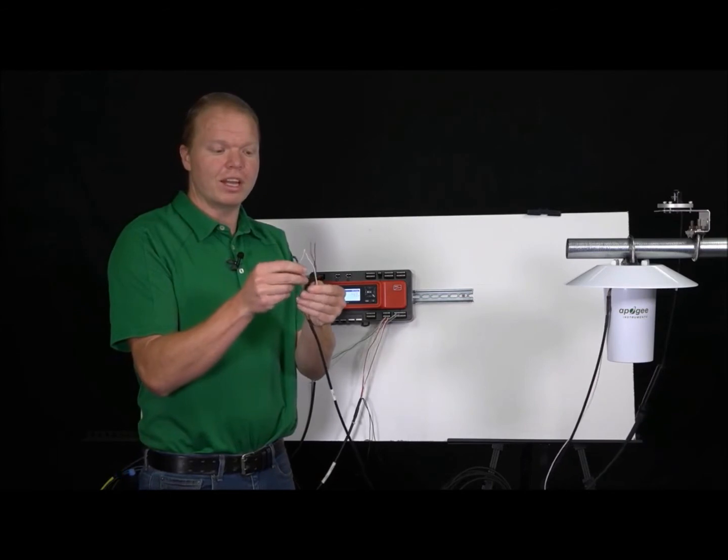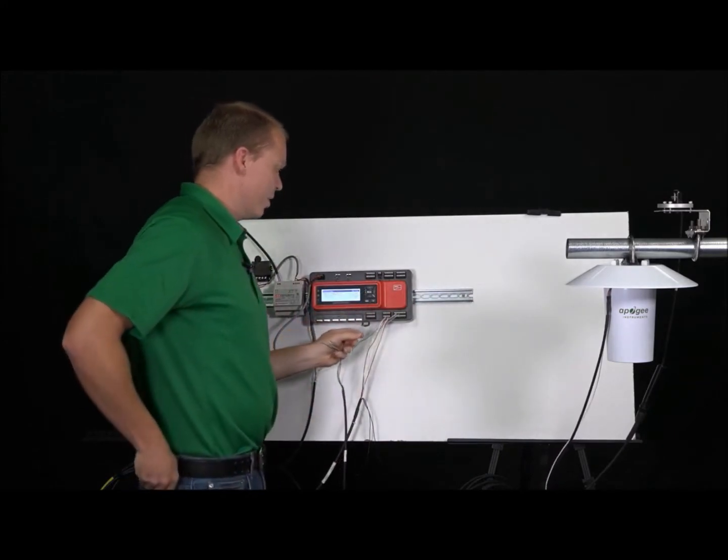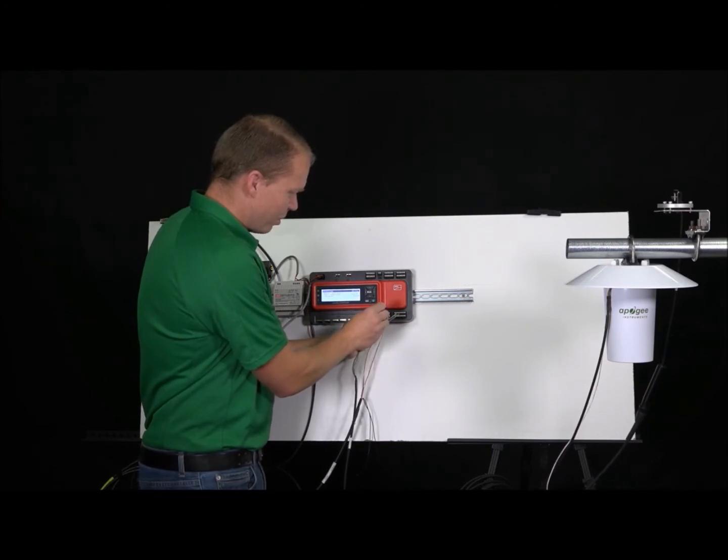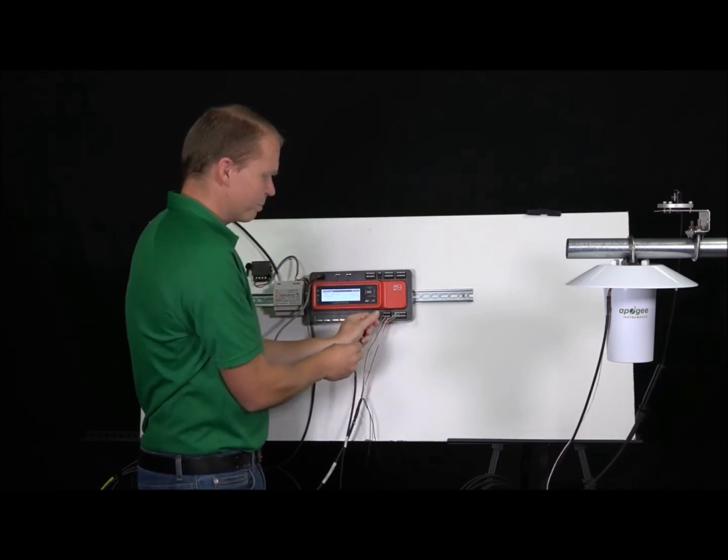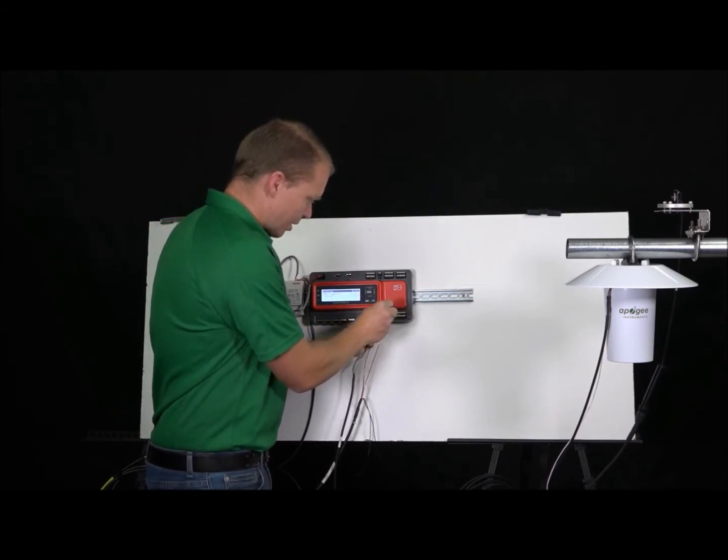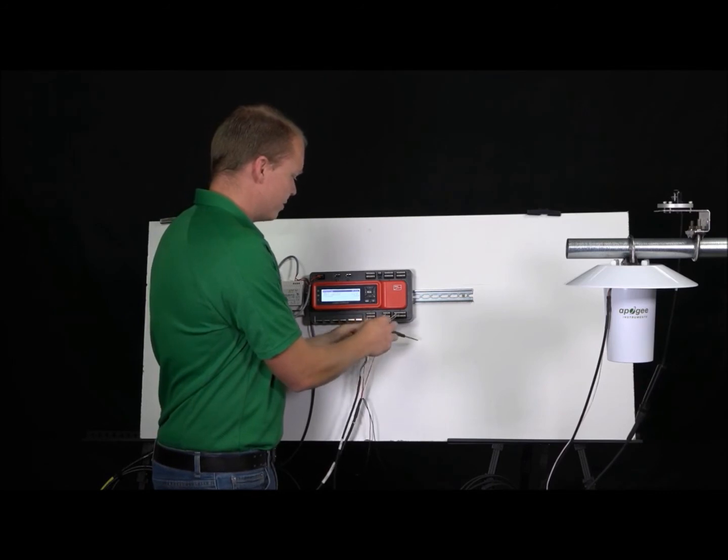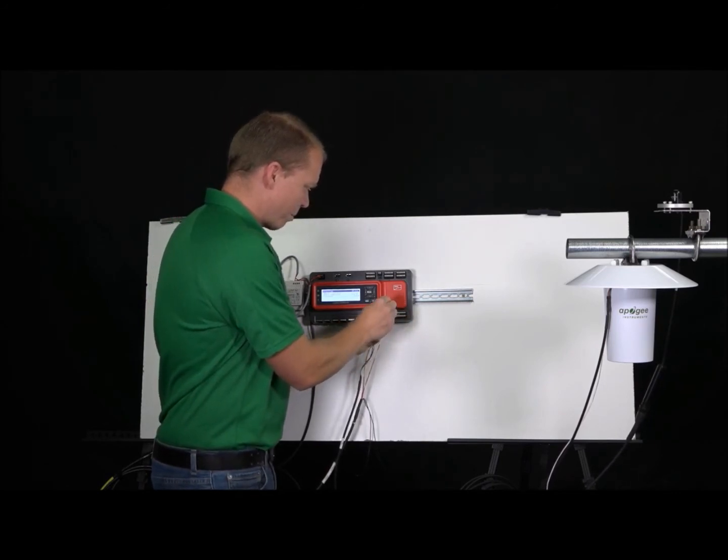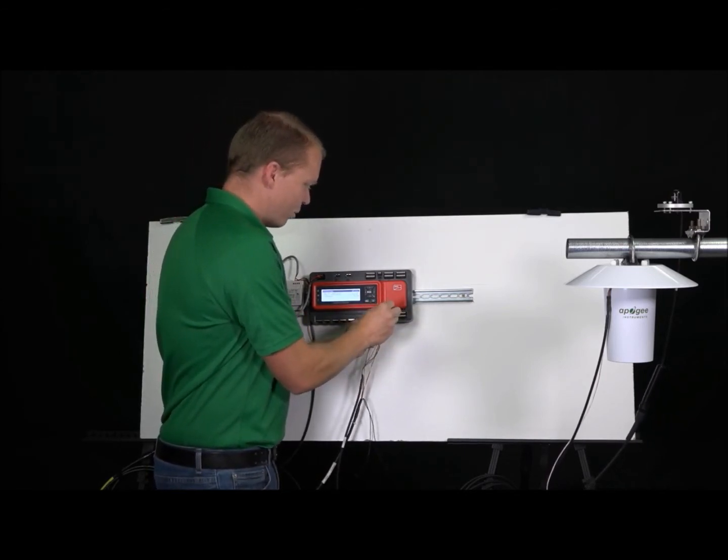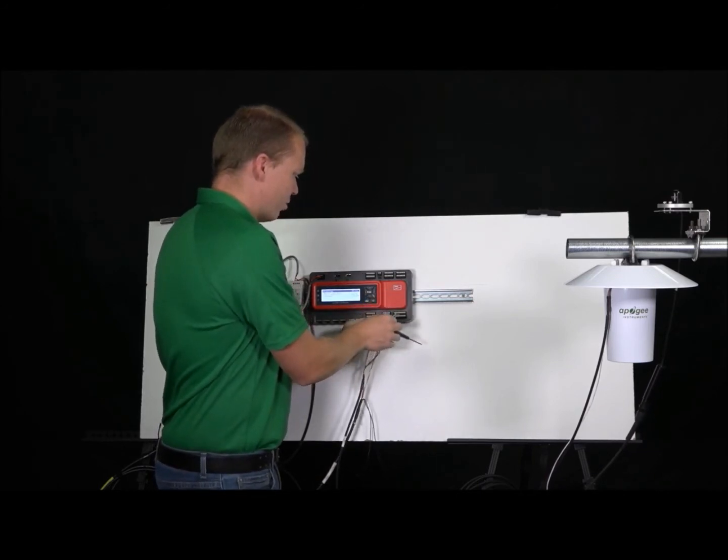So this one comes with five conductors. It comes with a shield, a red, a black, a green and a white. And we'll just be using all five of these conductors. So we're now on X7 row A. We're going to start right here. And we're going to put the shield in first, in the first terminal. The second one is going to be the white conductor. Then the next one is going to be the black conductor. Then we have the green conductor into the fourth terminal there. And then we have the red conductor.